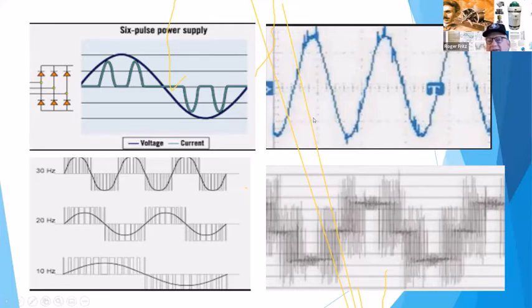So what we're doing with the VFD is we're actually regulating this PWM, which is then changing the current to the motor. And so we can go anywhere, like this is a 10 hertz, but you can see the pulses are spread out, and then this goes up to 20 hertz. The pulses are a little bit closer, and then they're going further. And inside of a VFD, they also have what they call carrier frequency, meaning how fast are these pulses happening. Some of the earlier drives, or VFDs, same thing, were just 6 pulses, meaning they had six pulses trying to control that waveform.